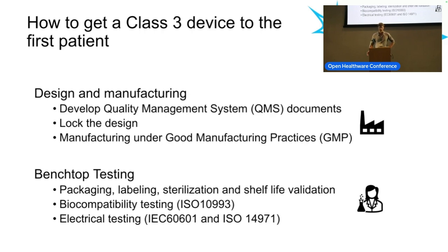Beyond the design stage, there's also a huge amount of requirements around benchtop testing. This includes things such as biocompatibility testing, making sure that nothing dangerous is leaching out of the device or that the materials won't interact with the body badly. It also involves, especially for our type of device, a lot of electrical testing, making sure that your device won't electromagnetically interfere with other things in the hospital, or making sure other things in the hospital won't interfere with it in a way that causes damage or could hurt the patient.